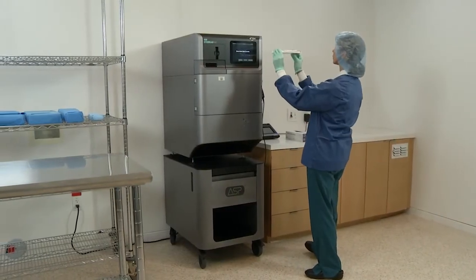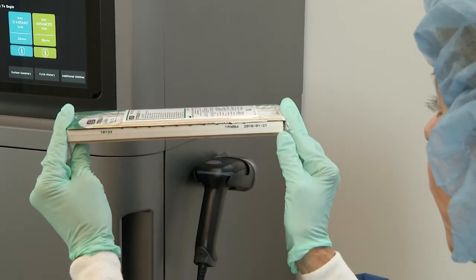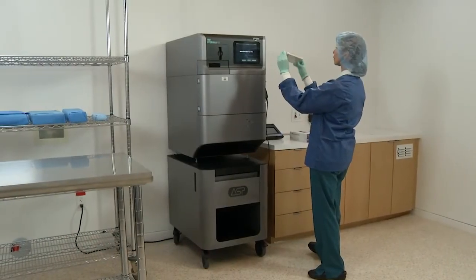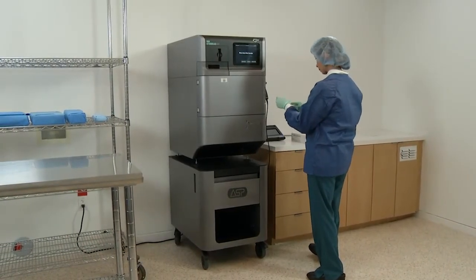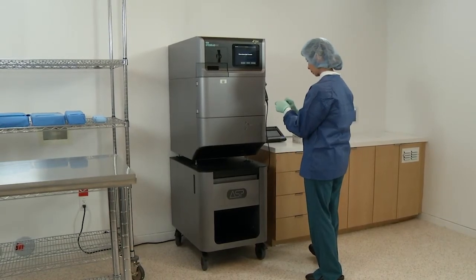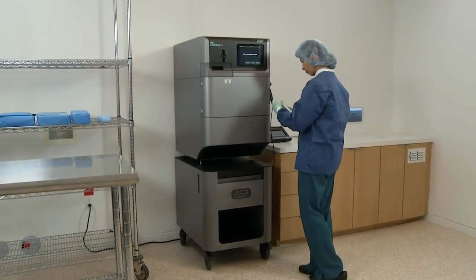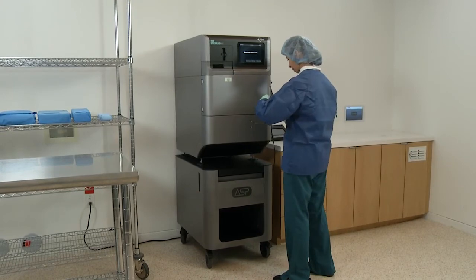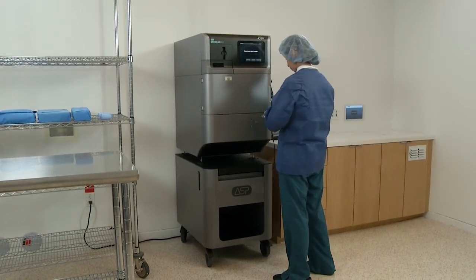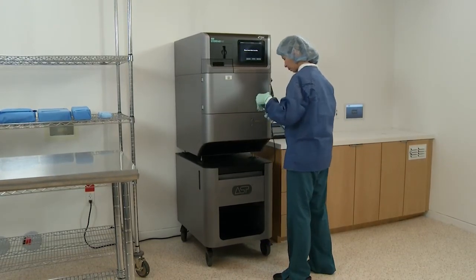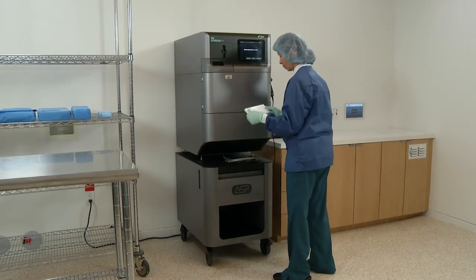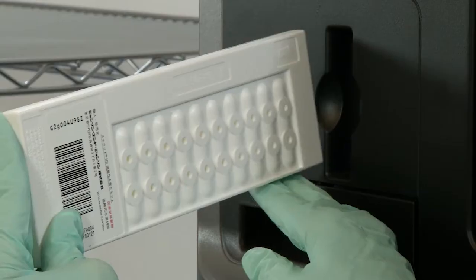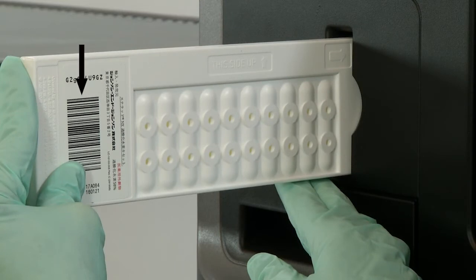Next, look at the package carefully before opening it. Check the expiration date before using a cassette. Do not use an expired cassette. If you see droplets of moisture, do not open the package. It is possible that hydrogen peroxide has leaked inside the package. Refer to the cassette Instructions for Use for proper handling instructions. Finally, insert the cassette into the cassette slot, making sure the barcode faces the display.